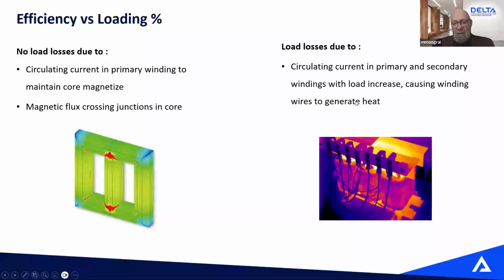So the more you apply load on your transformer, the more ampacity current will run through your windings, the more heat rejection you'll have on your coil winding wire, so the more losses. So ways to make a transformer more efficient is to lower those no load losses in the core and increase the size of the wire for your coil.